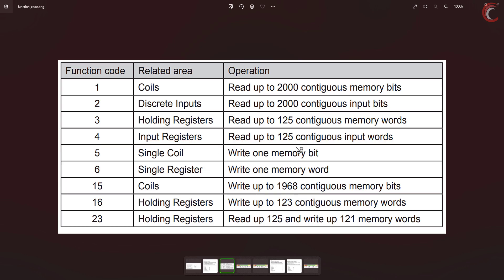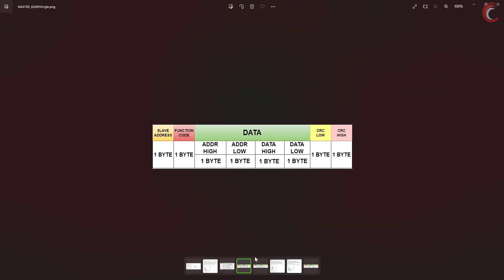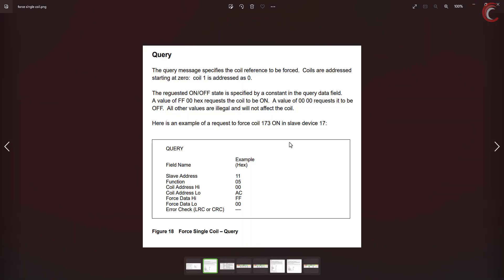The TX data format for function code 5 is going to have a total of 8 bytes, with the data field consisting of 2 bytes for the coil address and 2 bytes for the data. Although we are writing a single coil, which is 1 bit in size, we still need to send 2 bytes of data. To set the coil, we send 0xFF followed by 0x00. To reset the coil, both bytes should be 0x00.